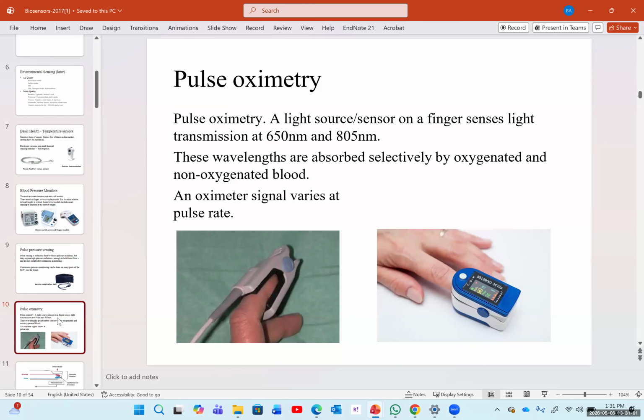So now another type of sensor that we have is called a pulse oximeter. This device measures two things. One, it measures heart rate. And the second thing that it can measure is the oxygen saturation level. Oxygen saturation level is very important, especially for someone with a lung disease or something like that. And if it's just measuring pulse, it will use one light beam around 650 nanometers. If it's measuring both heart rate and oxygen level, you need two different light beams.